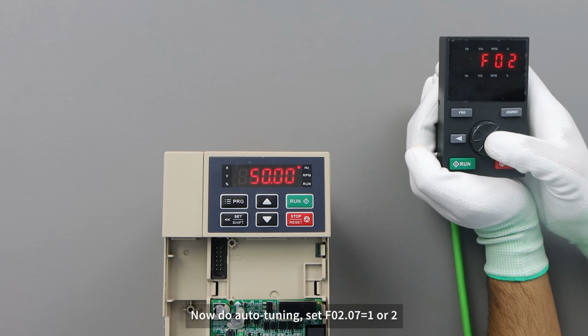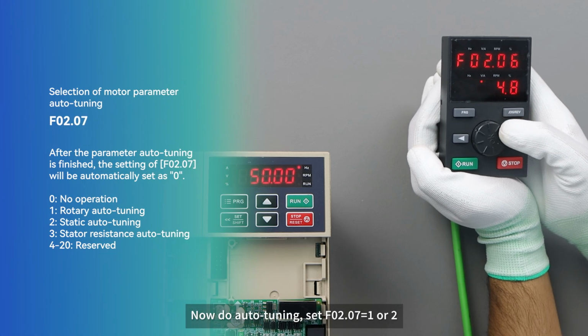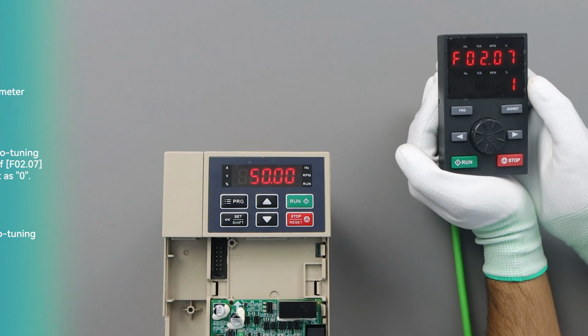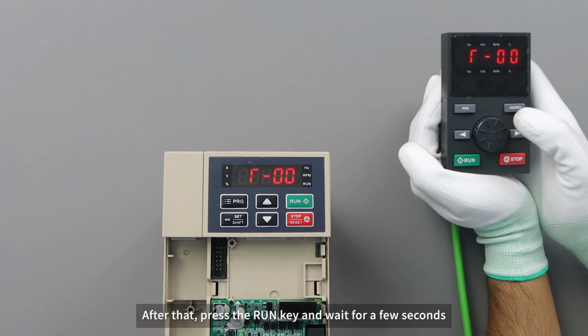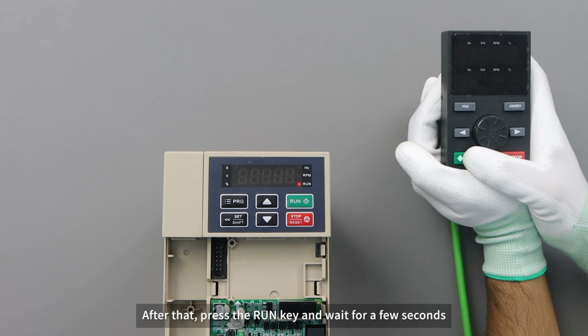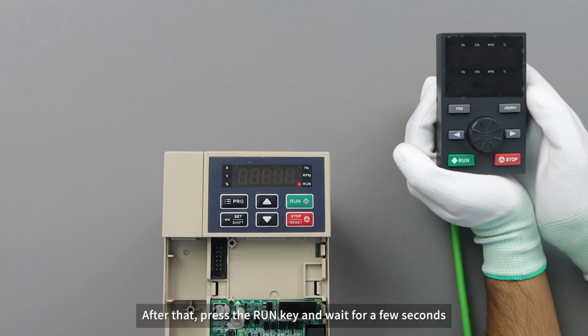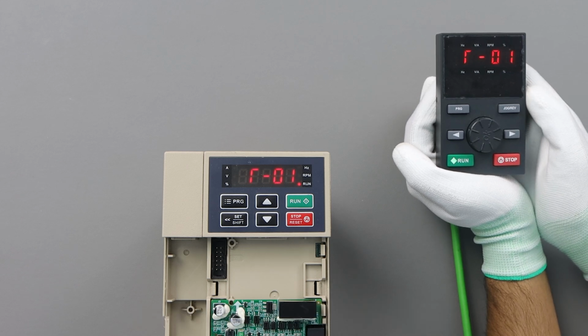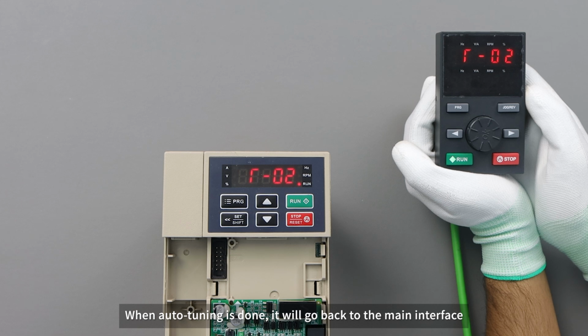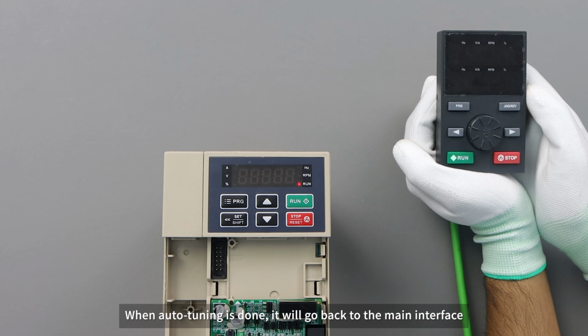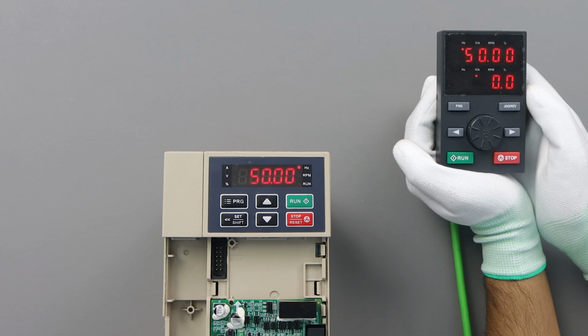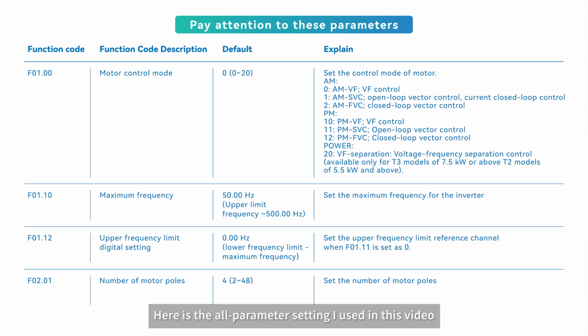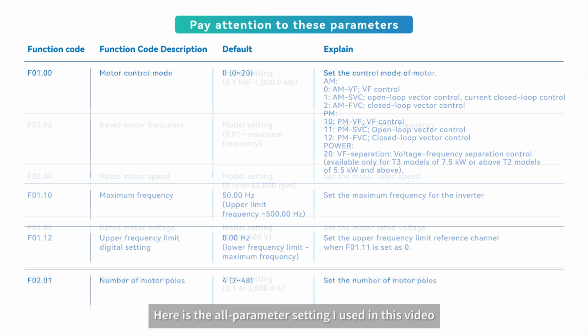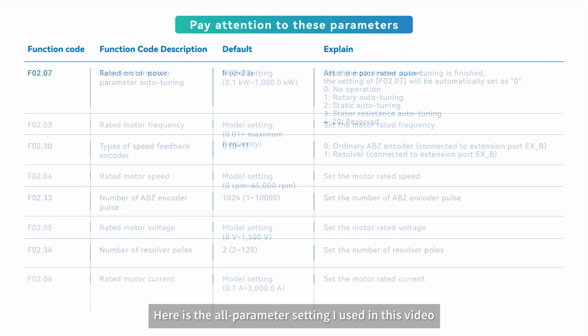Now do auto tuning. Set F02.07 to 1 or 2. After that, press the run key and wait for a few seconds. When auto tuning is done, it will go back to the main interface. Here are all the parameter settings I used in this video.